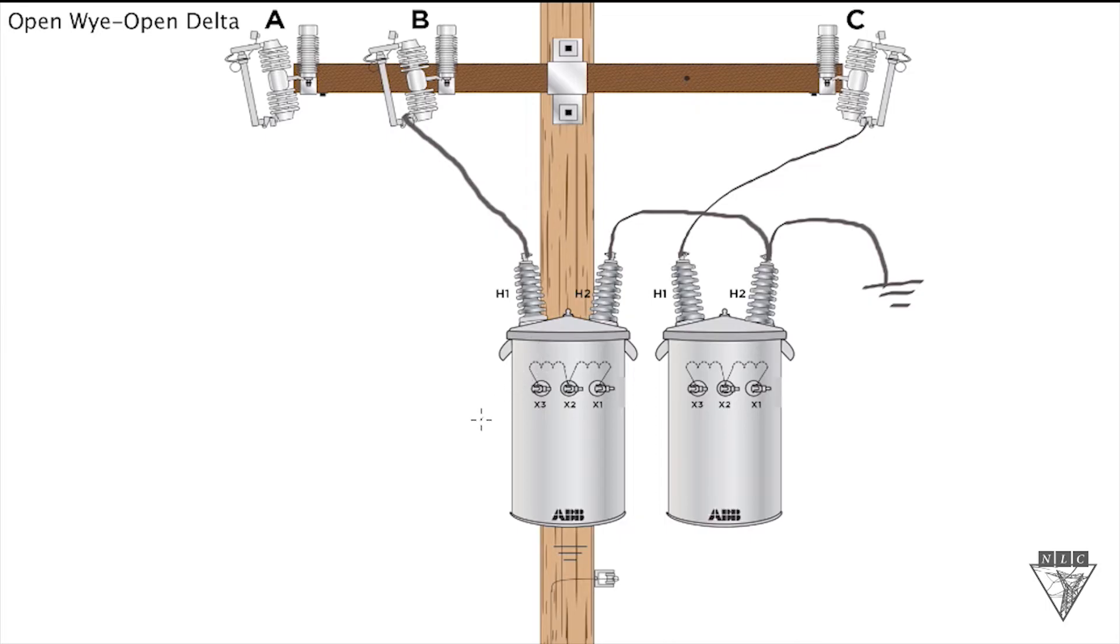Okay, let's move on to the secondary connection. On the secondary side, we're only going to utilize one X2 bushing as our neutral. We're going to take it to ground on the center transformer. Label it as our neutral. So there's our neutral.